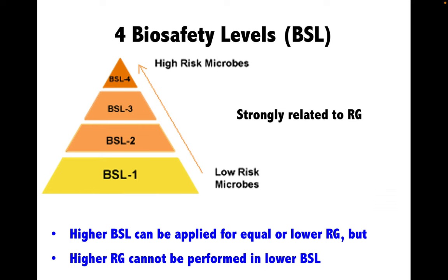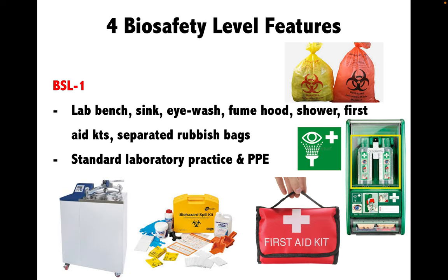Let's see a brief detail of each BSL. BSL 1 must be comprised of a lab bench, sink, eyewash station, fume hood, emergency shower, first aid kit, separated waste bags, and must be operated under standard laboratory safety with appropriate PPE.